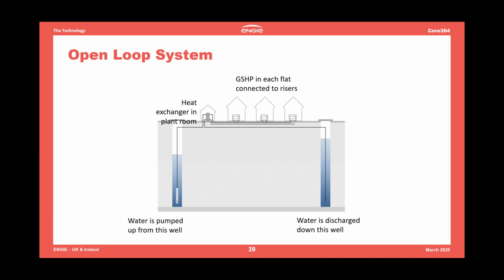So beneath these tower blocks, once you've got to about 60 meters depth, we're into an underground aquifer that has effectively a limitless supply of water. We are pumping that water up from that well. We pass it through some heat exchangers in the plant room, and these heat exchangers are just located in the ground floor areas of the tower blocks. And then through that heat exchanger, the water then gets discharged back down a second well that's drilled on site, and again roughly to 60 meters, so that the water is then just pumped back into the aquifer.